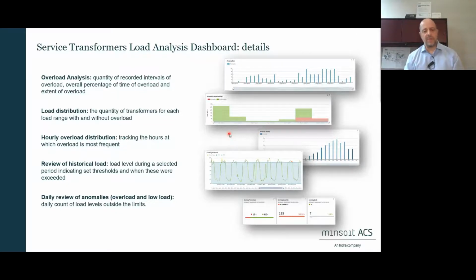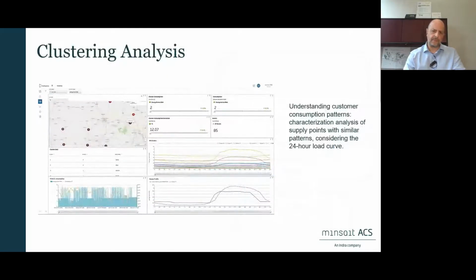We can review the historic load. So how many times that transformer, for example, has been for longer than three time intervals above 90% of its load. All this calculation can be run in the system. The algorithms are already there, but they can also be customized. Maybe you're not interested in 3 continuous time intervals, but you're interested in 5 continuous time intervals. That's a parameter that we can, of course, change in the algorithms.